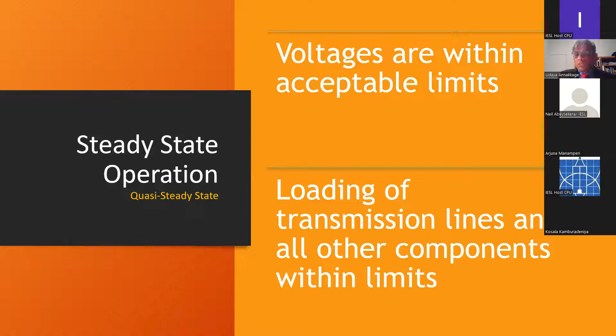What do we expect at steady state? We expect voltages to be within acceptable limits, and for most utilities, including I believe Sri Lanka, acceptable limits are within plus or minus 5% of nominal voltages. We also expect the loading of transmission lines and other components like transformers to be within operating limits. Additionally, the frequency of the power system must be close to nominal frequency, and for most cases, within plus or minus 1%.